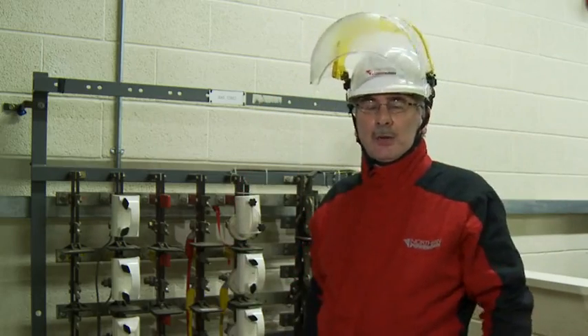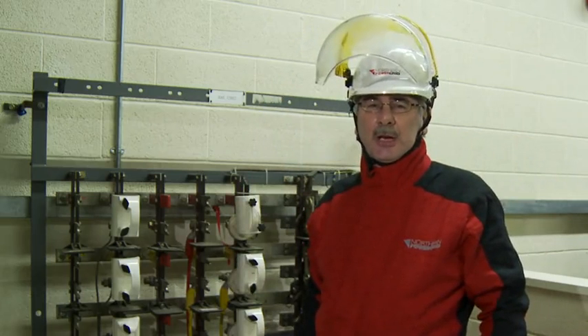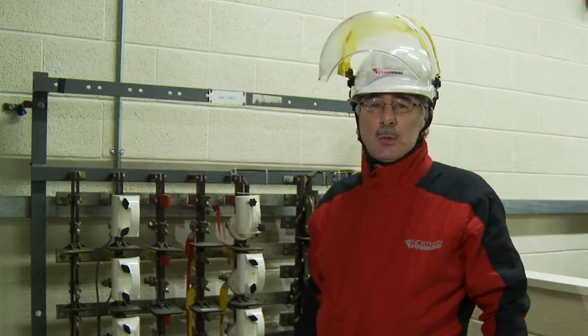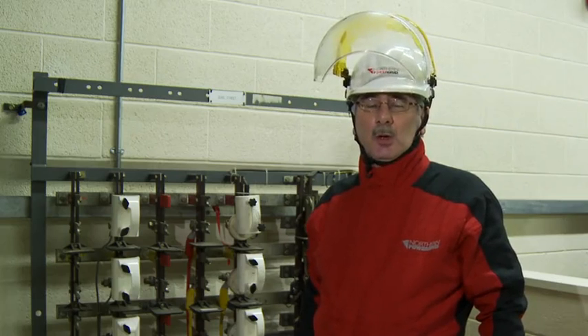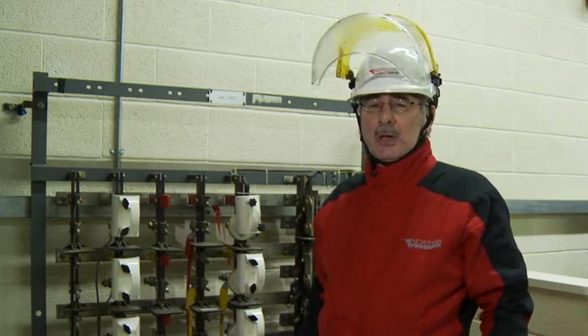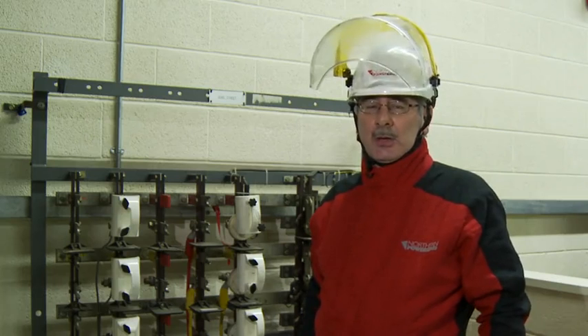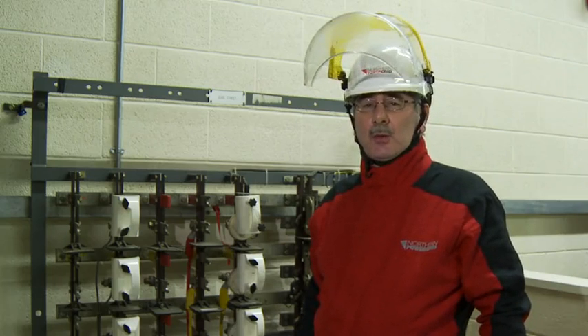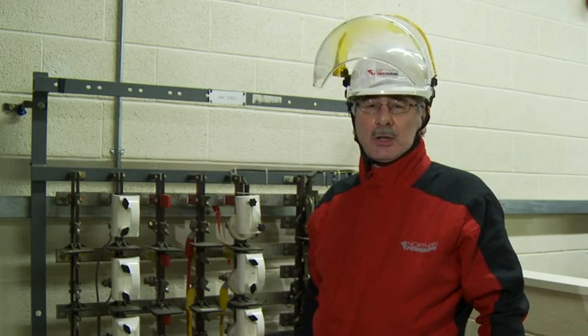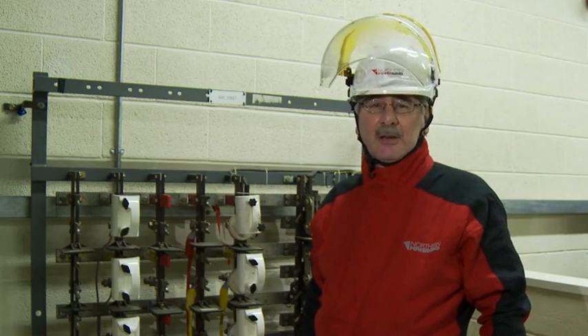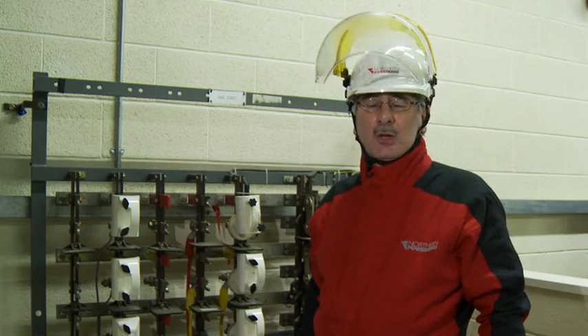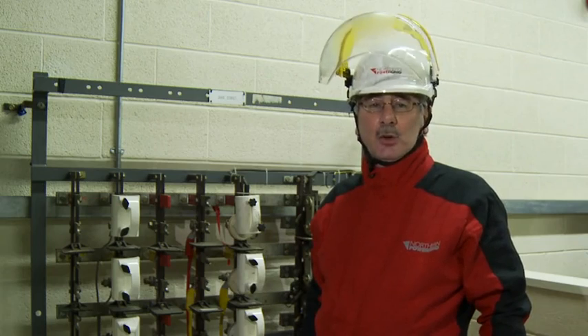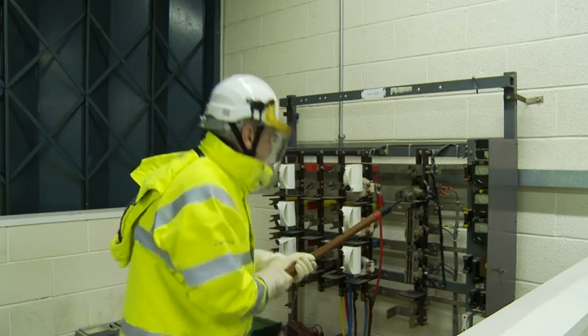Any activity on LV distribution boards requires a 2-layer protection system. In this case I'm using the polo shirt, cargo pant and coverall. If you noticed, I was at arm's length when I operated that fuse. That's very important. At 300mm from those bus bars, the arc flash incident energy level is something like 75 cals, whereas at 600, i.e. double the distance, it drops to less than 20.